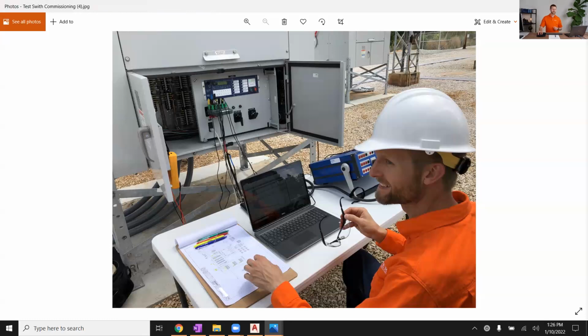But you can also use test switches not just for voltage and current PT/CT inputs. You can also use test switches to isolate DC inputs and outputs. And we haven't really gotten to the DC side of things yet. That will come later as we're looking at DC schematics. But I want you to be aware that you could, for example, use a test switch to wire the breaker auxiliary status contact, a 52A or a 52B that's coming into your relay. You can use a test switch to isolate that true power system from the back of your relay. Some people will use one test switch for an input, some will use two. Some want to just provide a way to isolate the signal. Some want to have isolation of both positive and negative DC. We'll look more at that in the DC context.